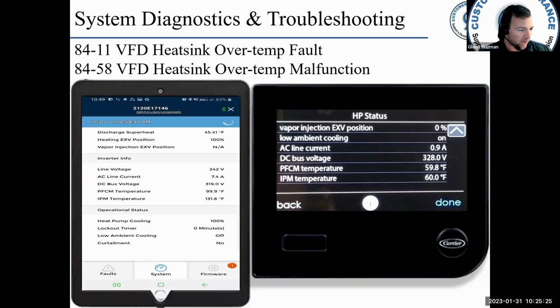What we're looking at here is the IPM or PFCM temperatures. Okay, so here's your PFCM, here's your IPM. When these temperatures approach 200 degrees, that is when you will start to see some of these faults, 8411, 8458. All right, so you can look on your HP status of the UI. You can look on your app and you can see PFCM temperature, IPM temperature. Make sure they both read the same.